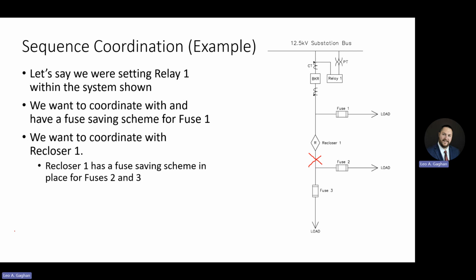There's also another scheme, not to be mistaken with sequence coordination, that's becoming very popular in Maine, called sequential reclosing, that I left off of here. Like I said, not to be mistaken with sequence coordination. But the sequential reclosing is just a way where both the recloser and breaker will trip, and then whatever's got a hot bus deadline will reclose. So the breaker would close, but it would not immediately trip back out. After a certain period of time, recloser 1 would reclose on its hot bus deadline, and then it would immediately trip out. The only difference is the reclosing cycle would be on a fast curve to prevent relay 1 from also tripping. So that's starting to become a pretty common scheme as well. So we'll leave it off here. There's kind of ways to accomplish these things.